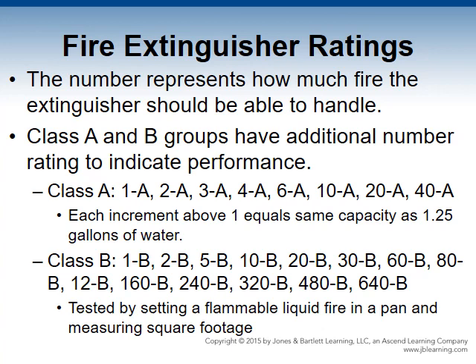Class A and B extinguishing groups have an additional number rating to establish their performance capability, representing how much fire the extinguisher can handle based on testing criteria. ANSI and UL 711 rating and testing was developed by UL and adopted by the American National Standards Institute. Class A extinguishers can be rated 1A through 40A; 1A through 20A are based on indoor tests, and 30A and 40A on outdoor tests. Each increment of 1 before the letter indicates the extinguisher has the same capacity as 1.25 gallons of water, so a 4A extinguisher equals 5 gallons of water. The higher the rating, the larger the extinguisher.